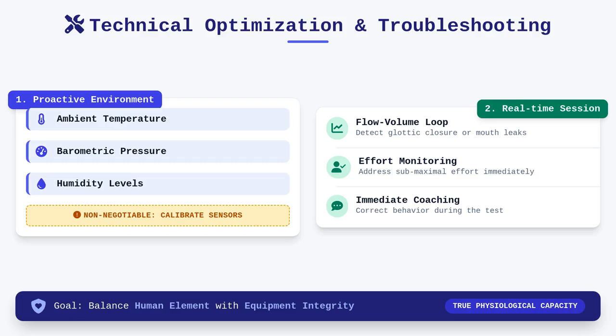Troubleshooting must be a proactive rather than a reactive process, starting with the ambient environment surrounding the patient. Variations in ambient temperature, barometric pressure, and humidity can significantly skew gas calculations, so verifying that your laboratory environmental sensors are calibrated and stable is non-negotiable. During a session, you should be monitoring the flow volume loop shape for signs of glottic closure or mouth leaks that would suggest the need for immediate coaching.